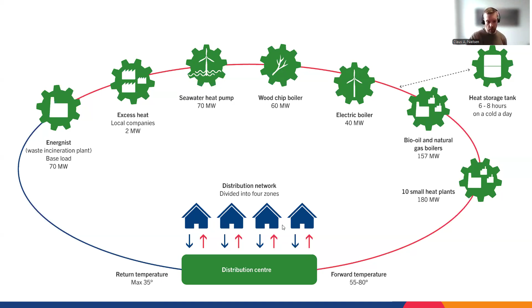As you can see, and as Raymond mentioned, the heat pumps in Esbjerg are operating. Since the 1st of January we've been producing a lot of energy, supplying around 20 to 30% of our energy mix, depending somewhat on seawater temperature. This year we had 2 days where we had to shut off, because the freezing point of seawater in Esbjerg was so close.